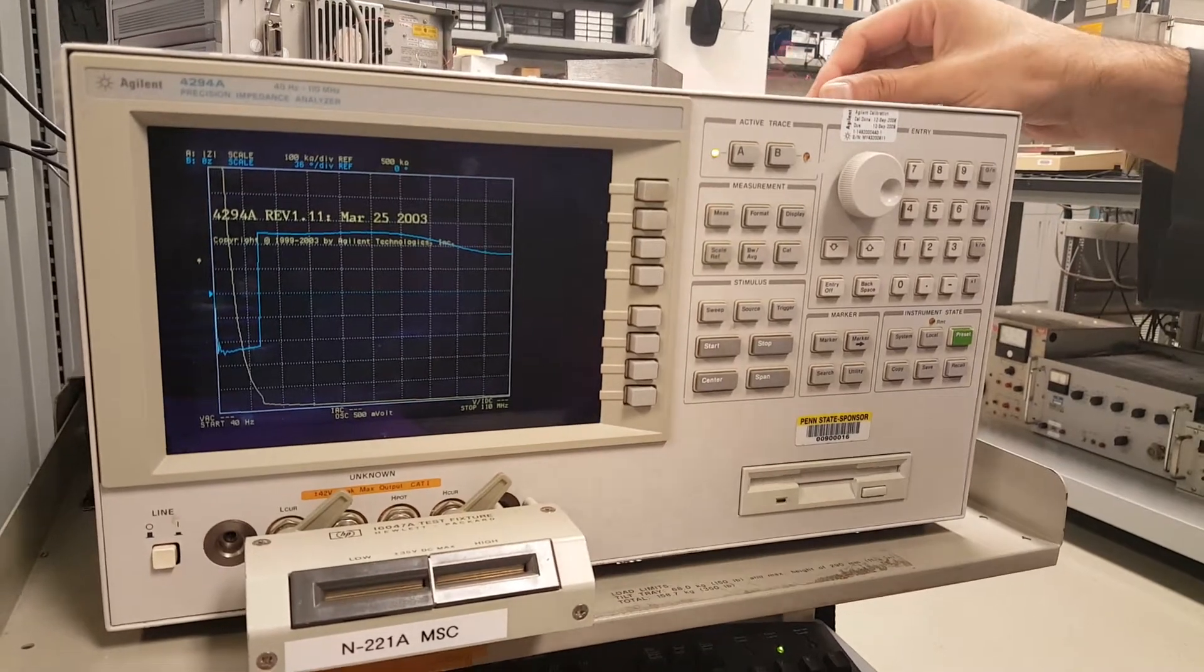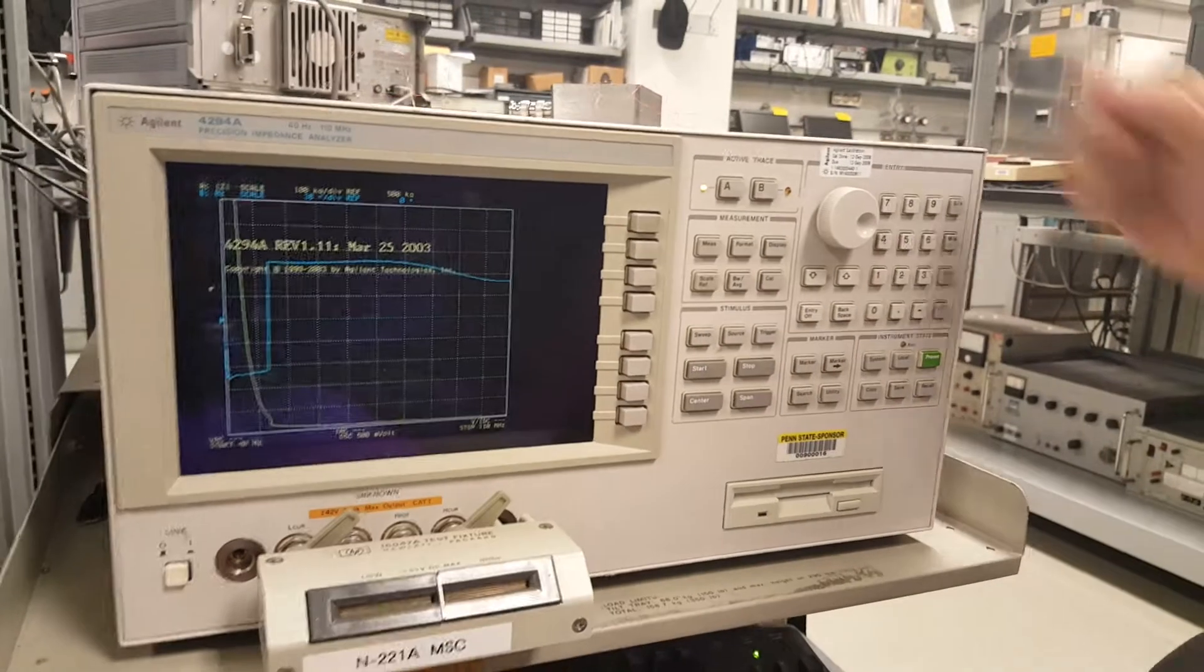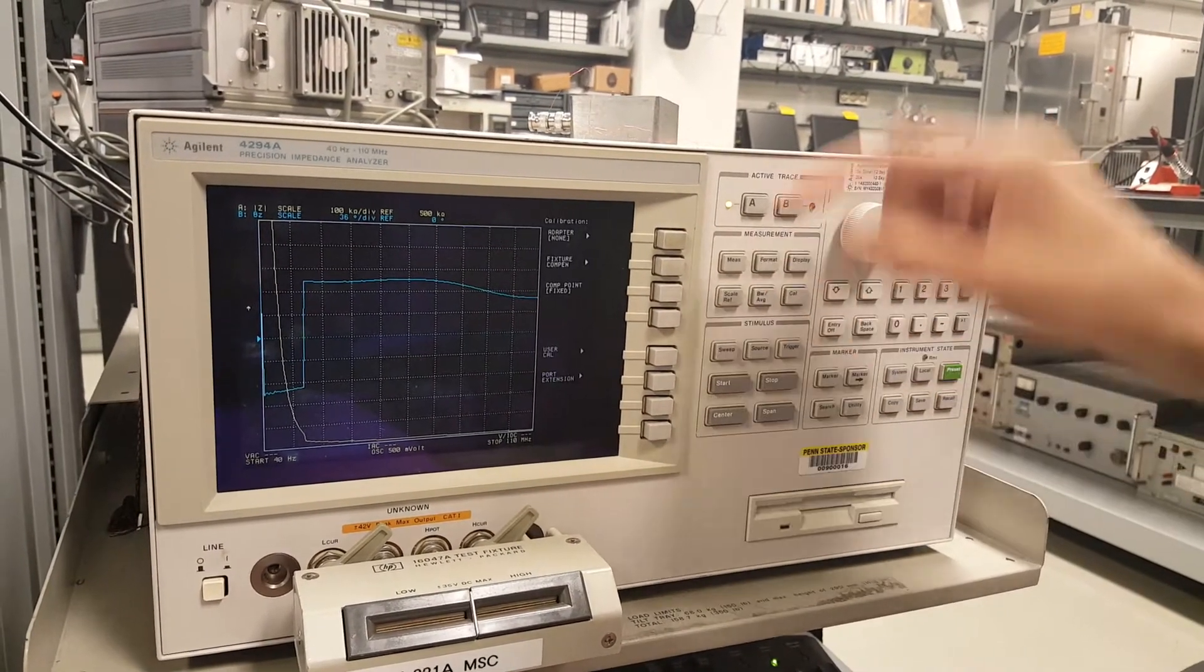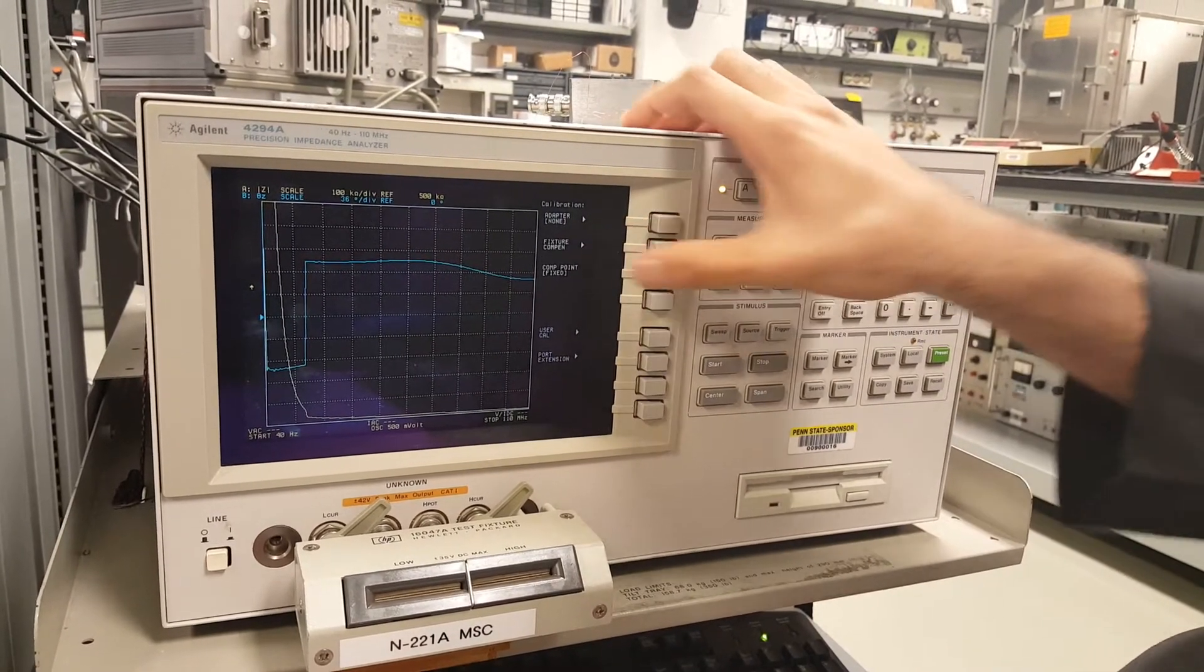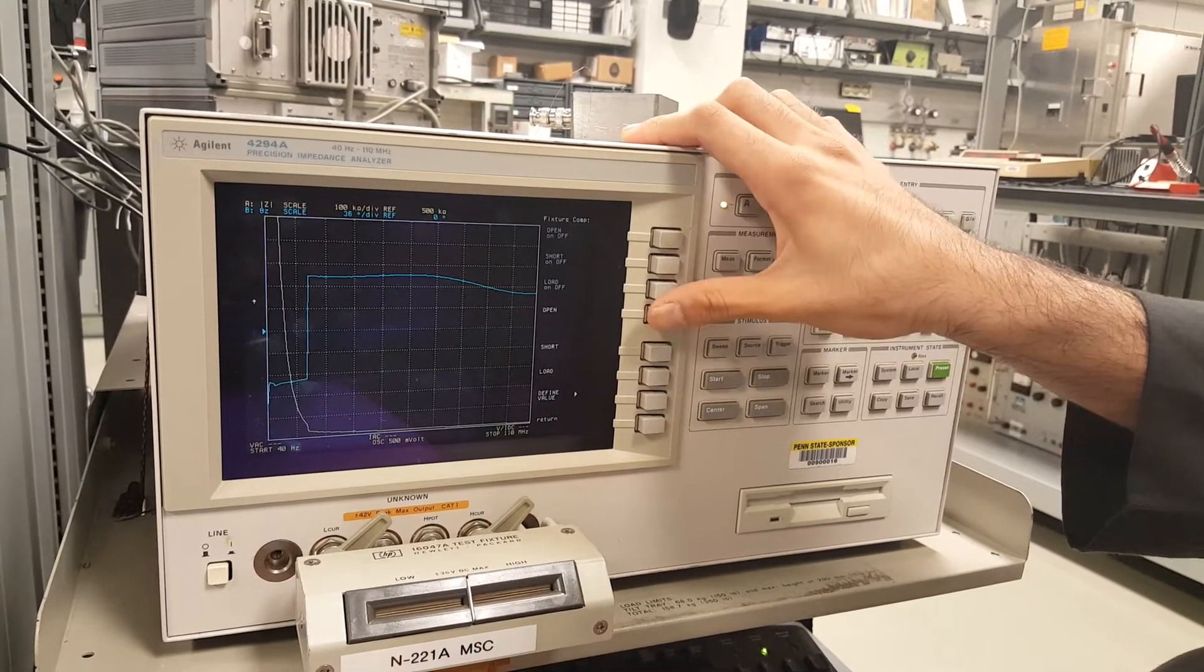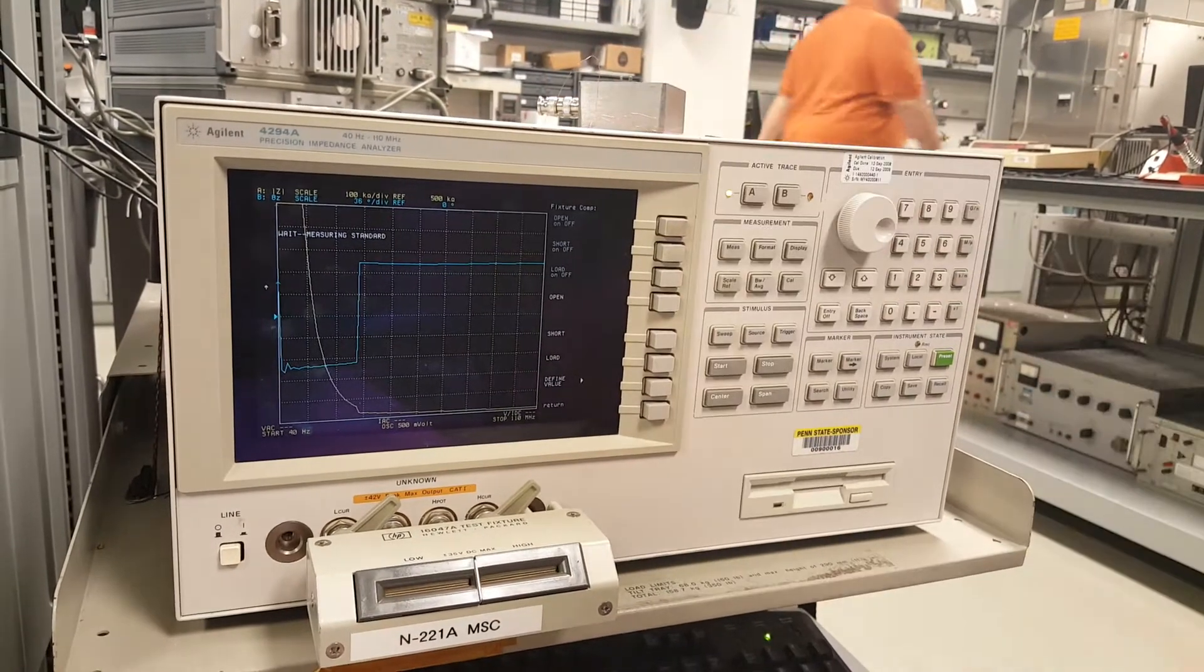Okay, so we're going to characterize the sample using the impedance analyzer. First, we'll go to calibration. We could say fixture compensation. Click that, and then you click open circuit. You click open here and this is measuring.